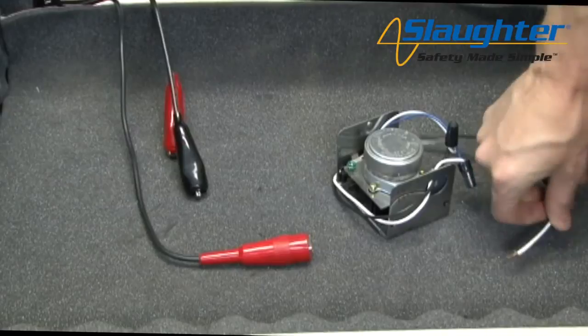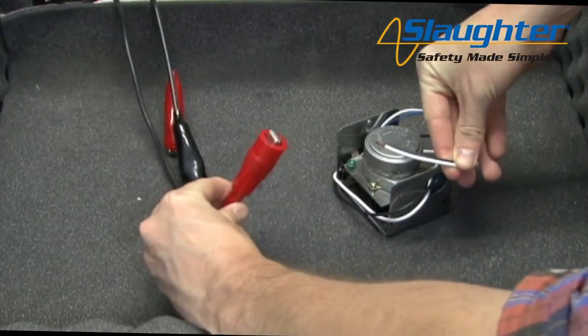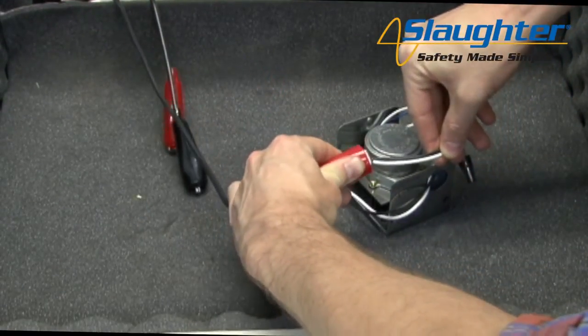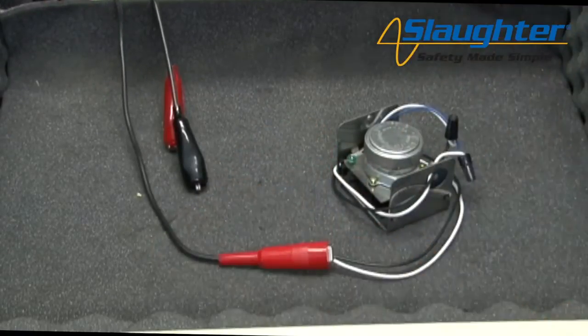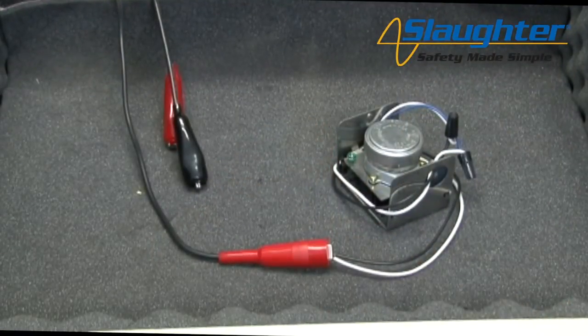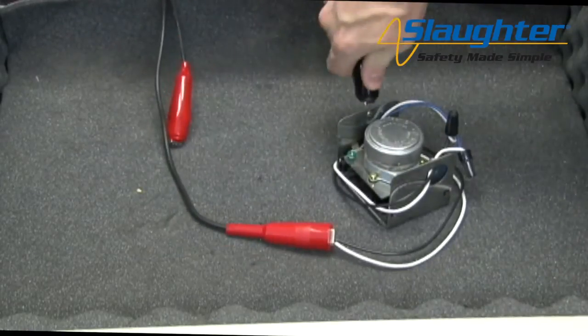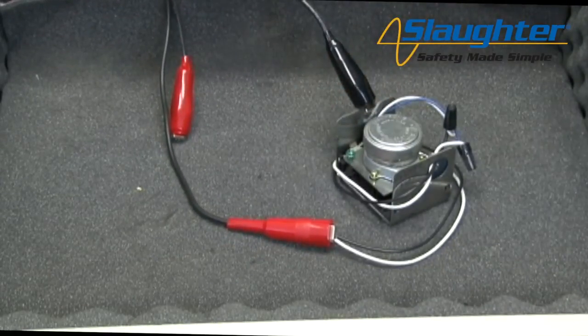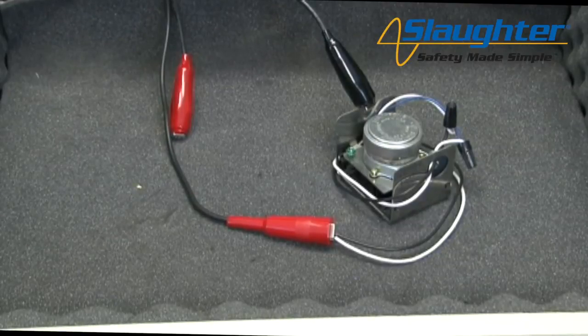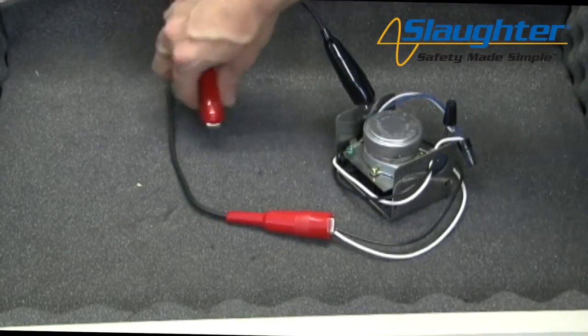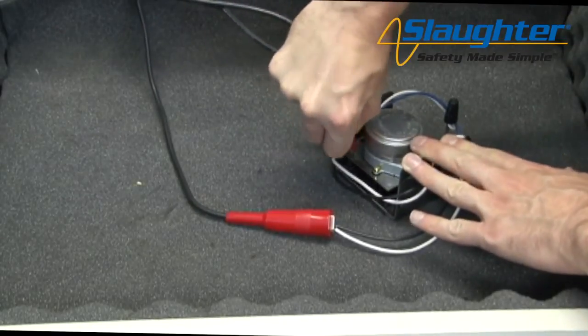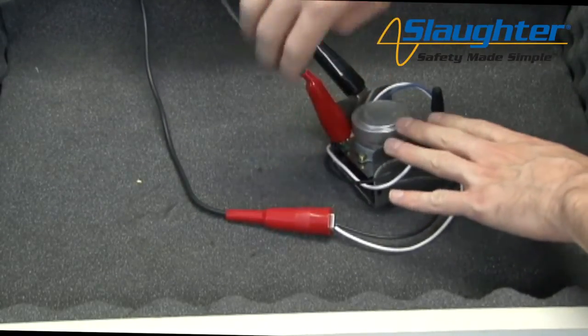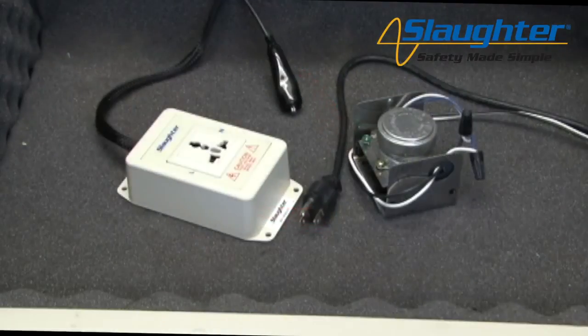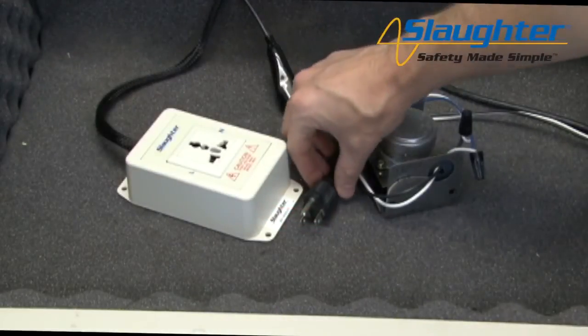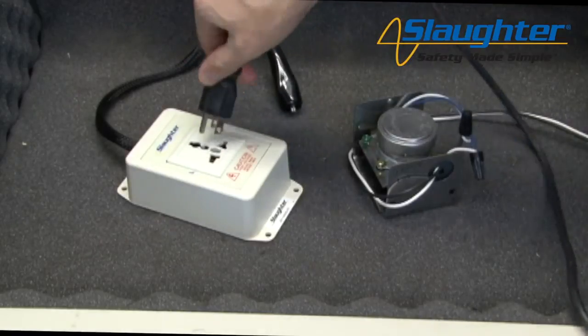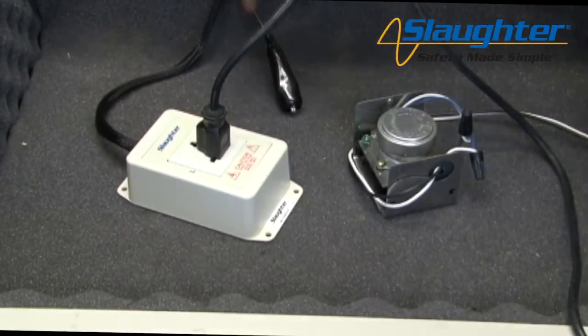Clip the high voltage lead to the mains conductors of the DUT. In this case, we're shorting the line and neutral wires, which are the black and white wires, to the high voltage lead. Next, connect the return lead to the chassis of the DUT. This allows for a return path for the leakage current so the unit can measure leakage through the insulation of the DUT. Finally, connect the high current lead to the ground wire or ground point. If using the adapter box, simply plug the product's 3-prong line cord into the adapter box and connect the return lead to the chassis of the DUT.